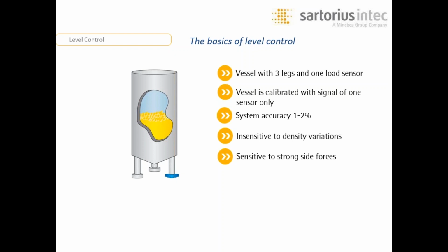This is especially valuable in situations where other measurement equipment has failed to yield acceptable results. If for some reason the product in the tank has a foamy consistency to it, sometimes radar doesn't work as well as the customer would hope. And if they don't have room or don't choose to add any type of glass or any other type of leveling, then the level by weight is a great system. It's highly affordable, and we'll cover a couple more here.